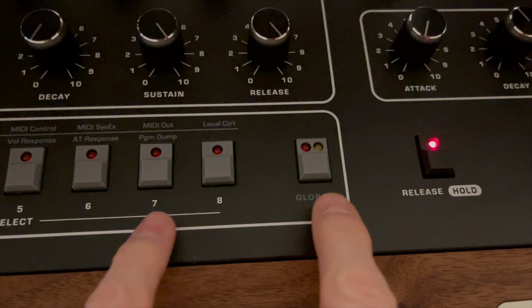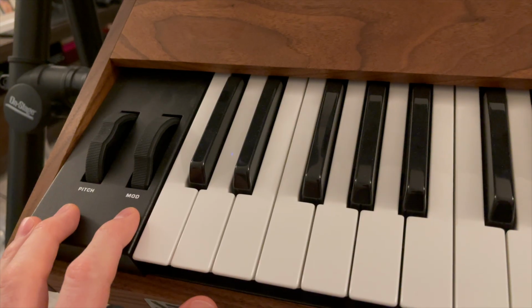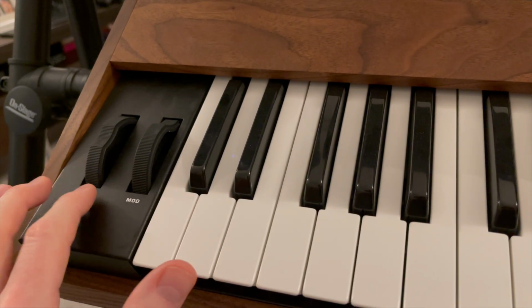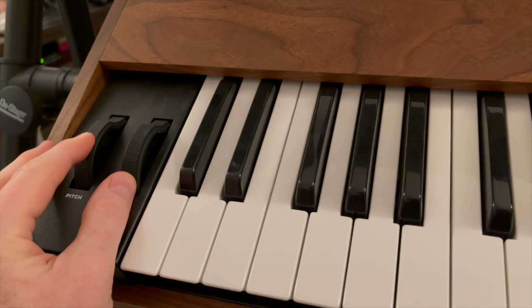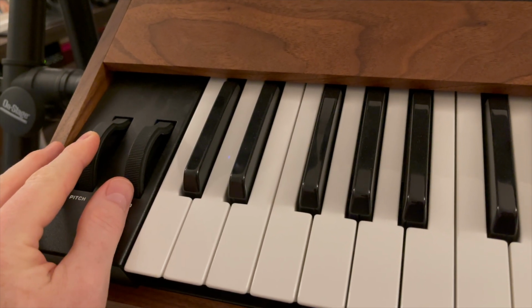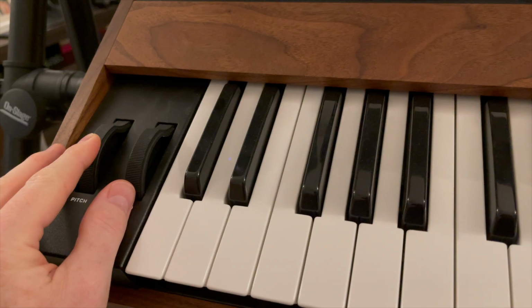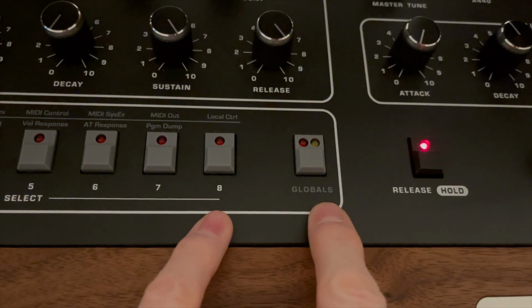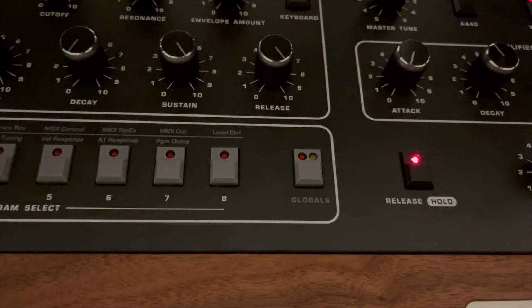Finally, set the mod wheel to its maximum setting. Hold the pitch wheel to its maximum setting. By holding the pitch wheel down to its maximum position, press and hold the globals button and Program Select button 8. The high points of both wheels are now calibrated, and you can play the Prophet 10 again to see if it's holding a tune. If not, run the tuning calibration one more time and give it another listen.